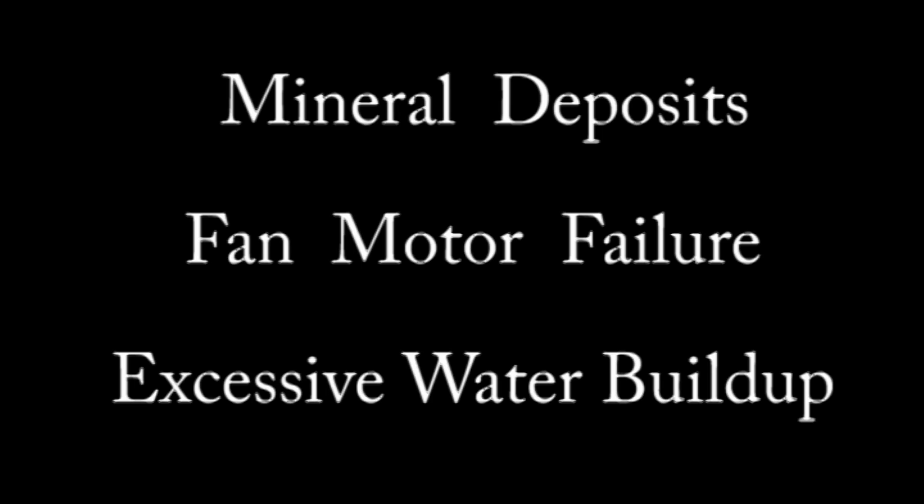I have seen a lot of products out there, and I know from experience, they work fine for a month or two. And then leaks develop, misters clog, and fins start getting mineral deposits. This all leads to one thing, total failure of the air conditioning unit.